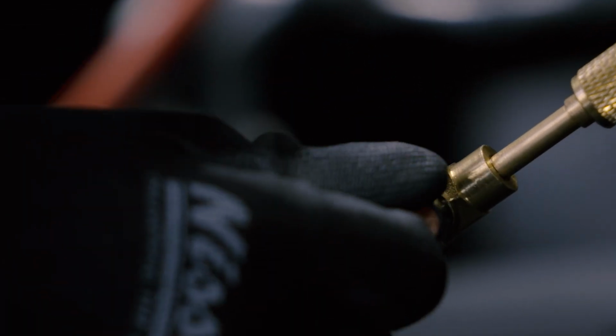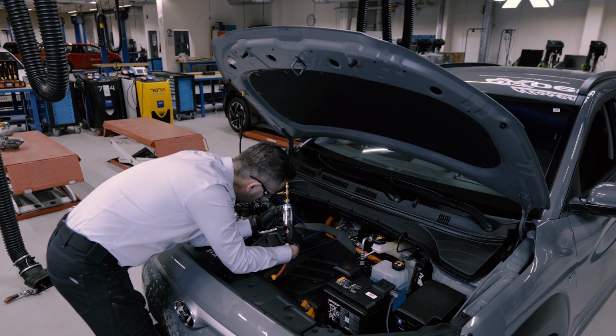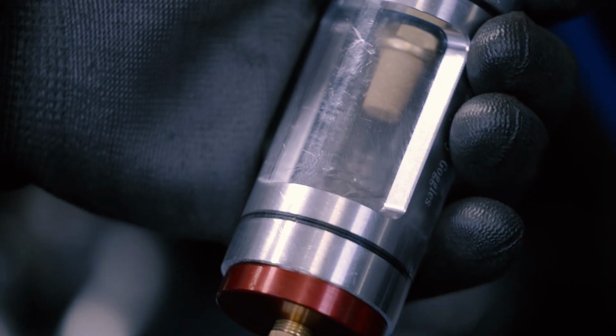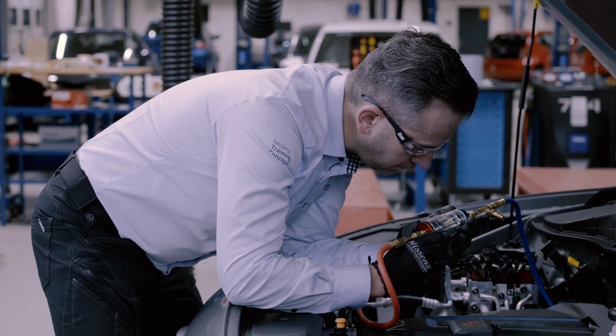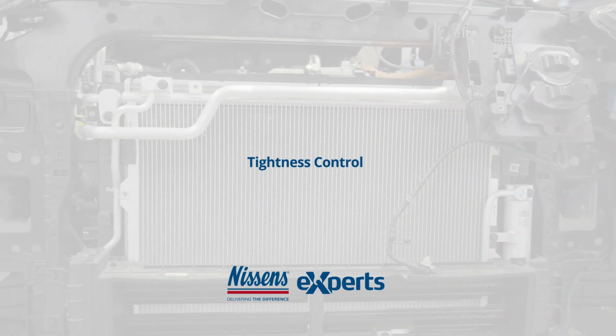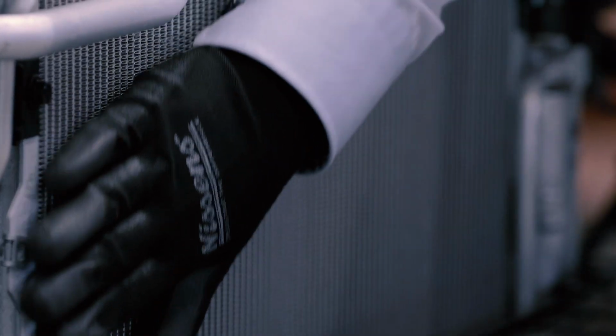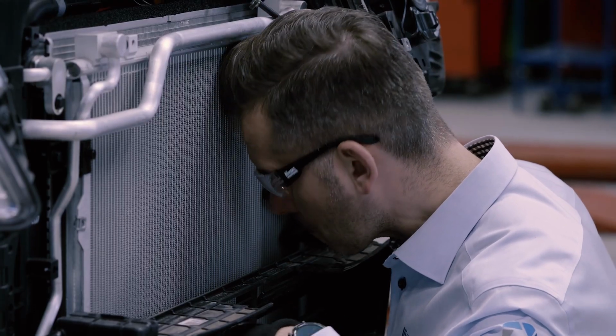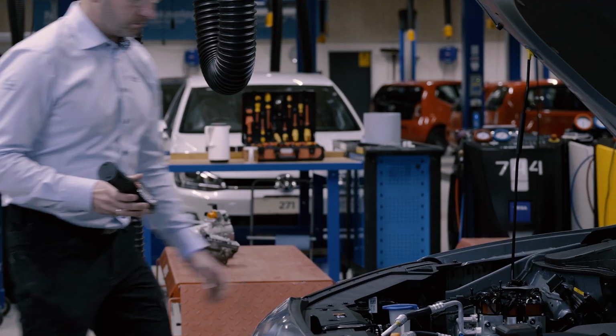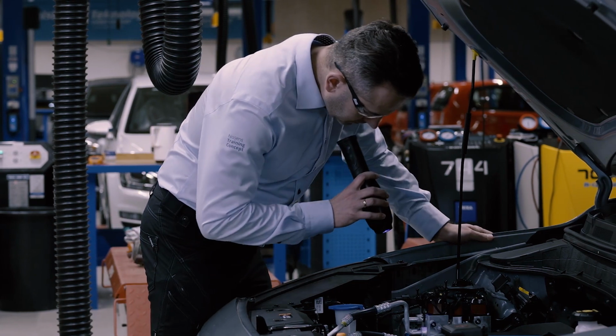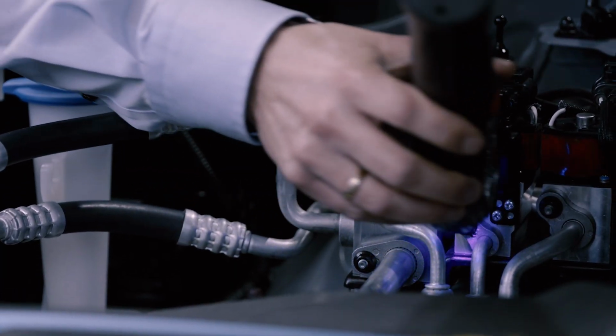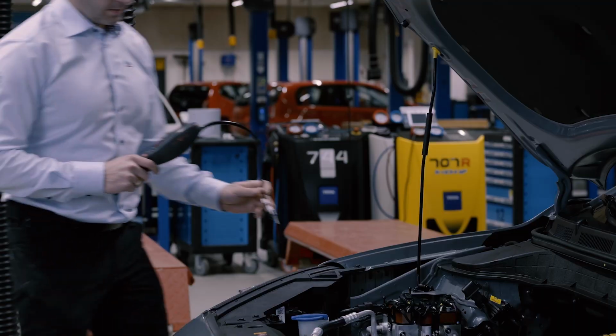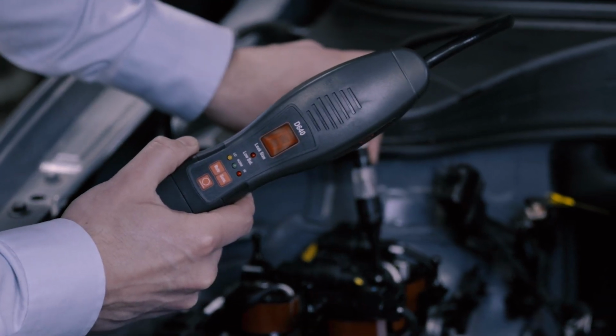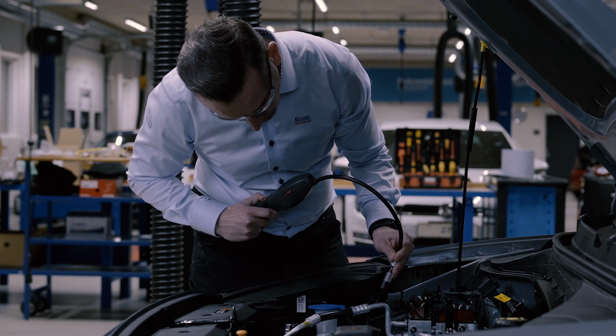Particles, debris, impurities, as well as improper use of additives, such as leak stop and UV dye, can lead to flow restrictions within thin passages of the system and provoke severe consequential failures. Depending on when in the process you will examine the loop tightness, you can apply one of the well-known methods. Start from a thorough visual control of the loop components and especially the couplings. UV dye detection, as well as a nitrogen-based check, can also be included, especially after bigger services like components replacement.